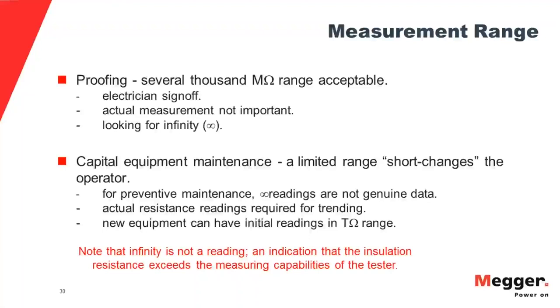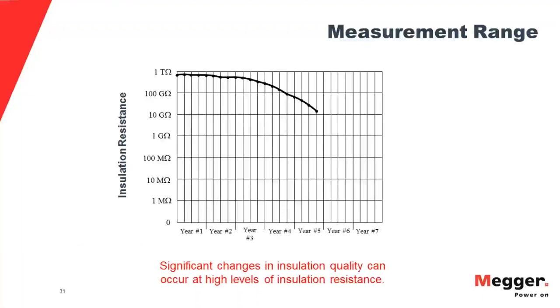If you have a tester that measures to that range, that's all you need to determine whether something is good or bad. But on the other hand, if you're doing long-term electrical maintenance, then you want to have higher numbers to work with. An infinity reading does not really tell you anything other than that you're over the scale of the tester. The thing you're testing is good, but you don't know how good. So if you're doing that type of testing, long-term maintenance for instance, then a high-range tester is good to have, and we'll take some further look at that.